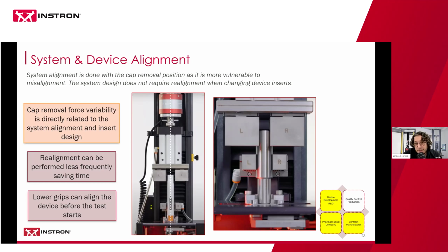And the system was aligned with the cap removal position in mind. That's important because that result is so closely tied to alignment. You have a lot more room for potential misalignment with the injection because you are just activating over an open hole. So we wanted to make sure that the critical region for alignment was the cap removal position, and everything was aligned based on that.